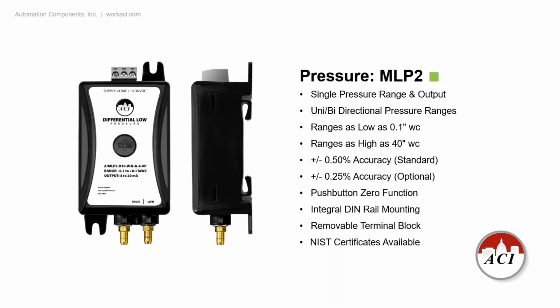So like the DLP, we offer the MLP2 too. Not universal or jumper selectable pressure ranges, outputs or inputs. Basically, this is what you get. So if you order a 0 to 1 inch with a 4 to 20, that is what you get. You do not have any jumper selectability. Now we do have bidirectional and unidirectional ranges on each of them. It does have the auto 0 push button in the front and a depluggable terminal block on the top. But as you can see, it does have the mounting feet or a DIN rail to mount it properly in the field.